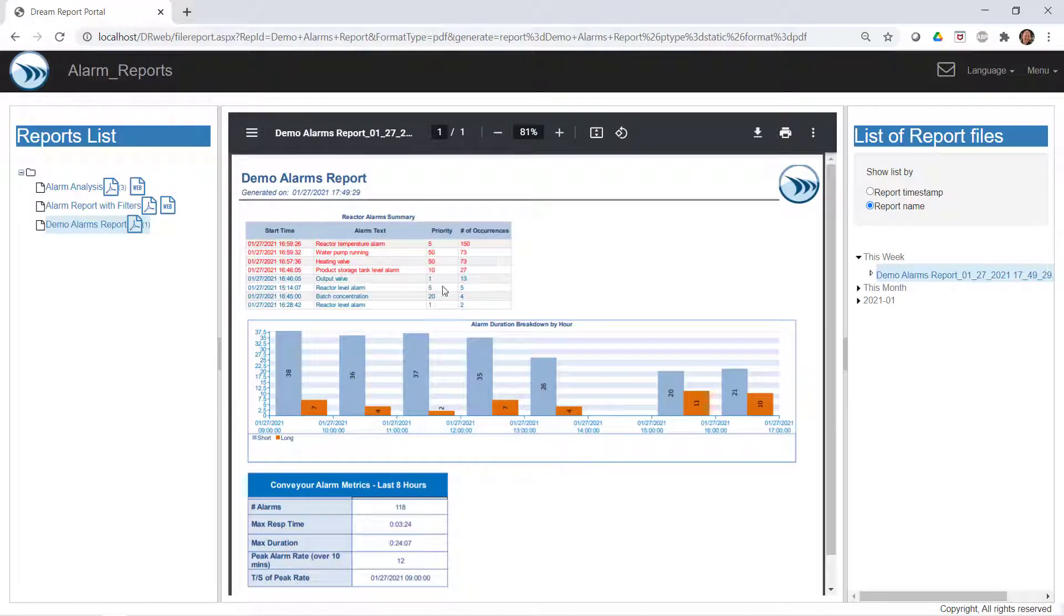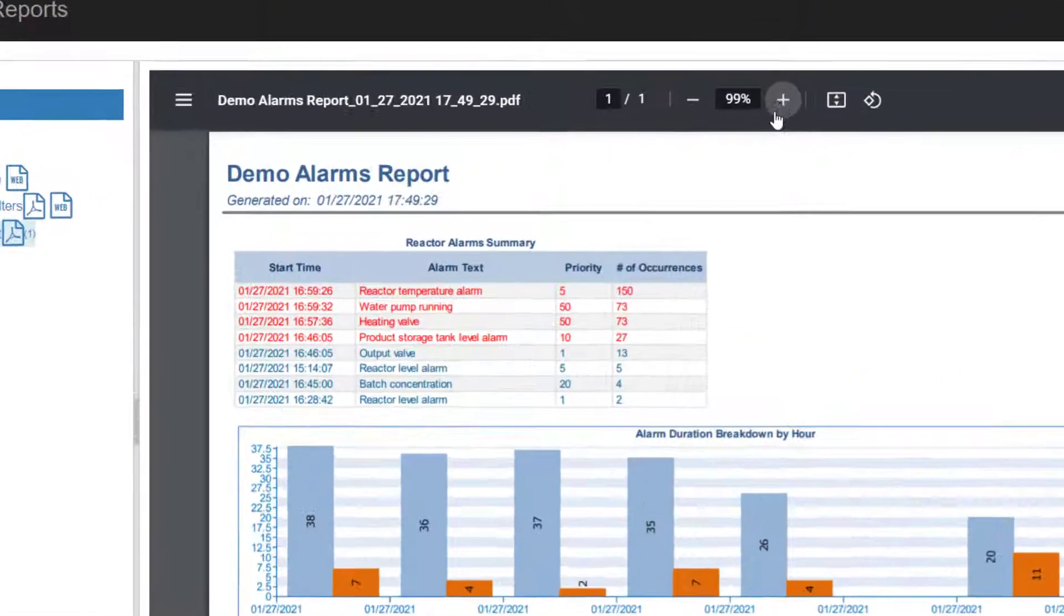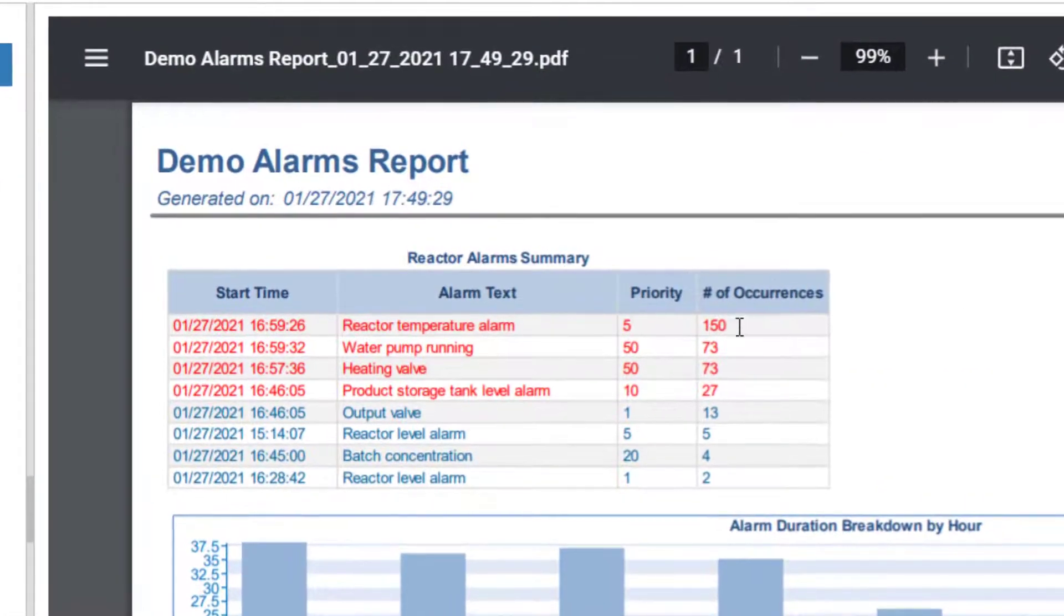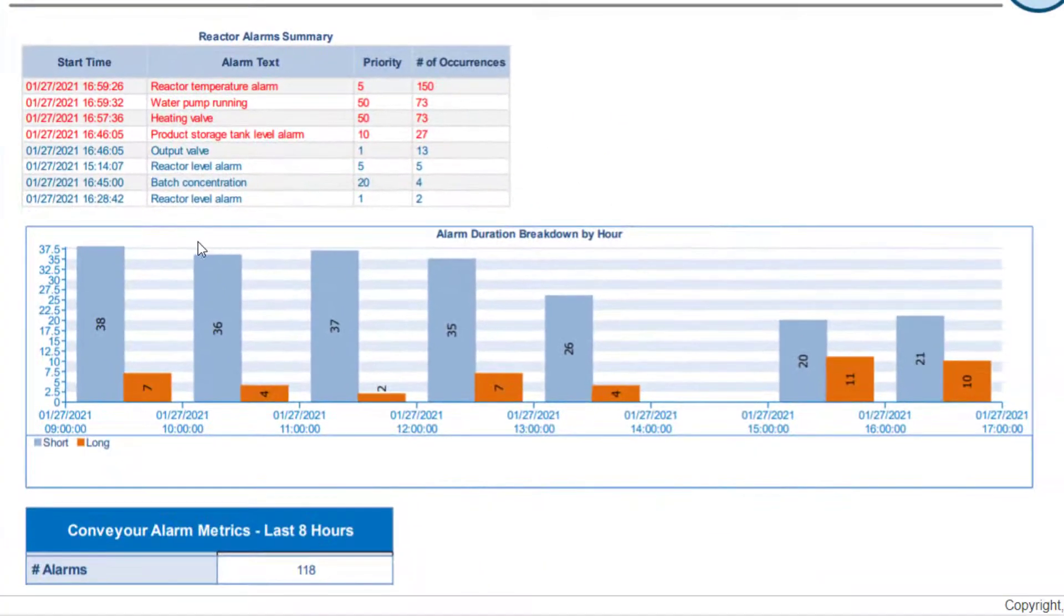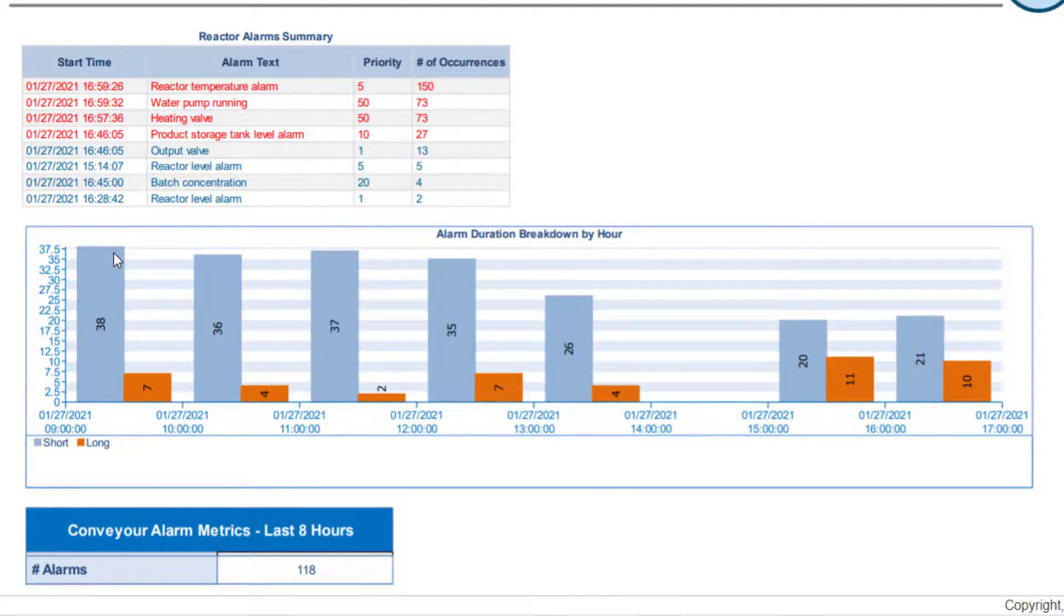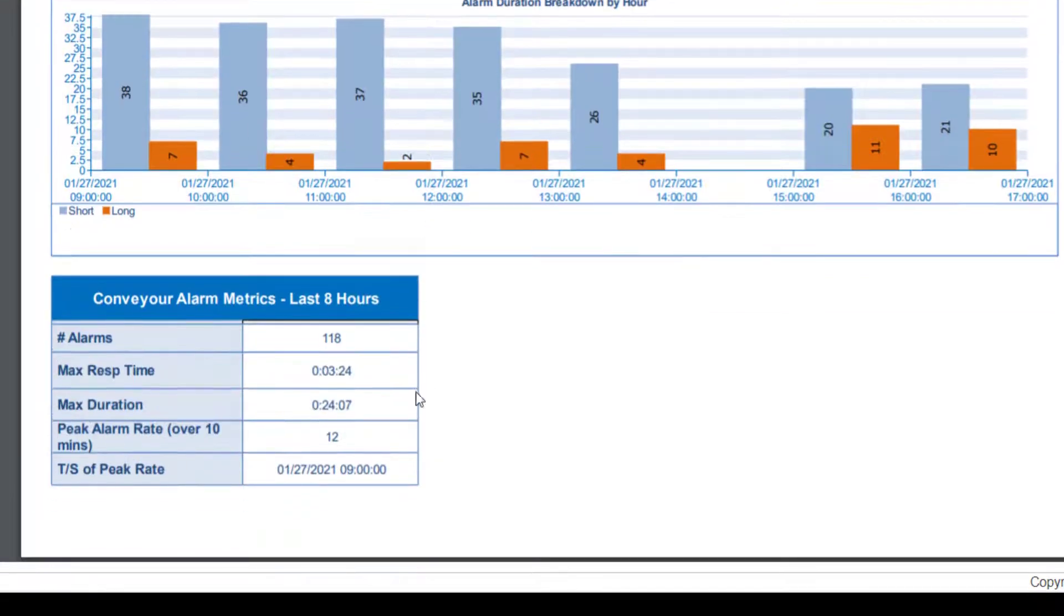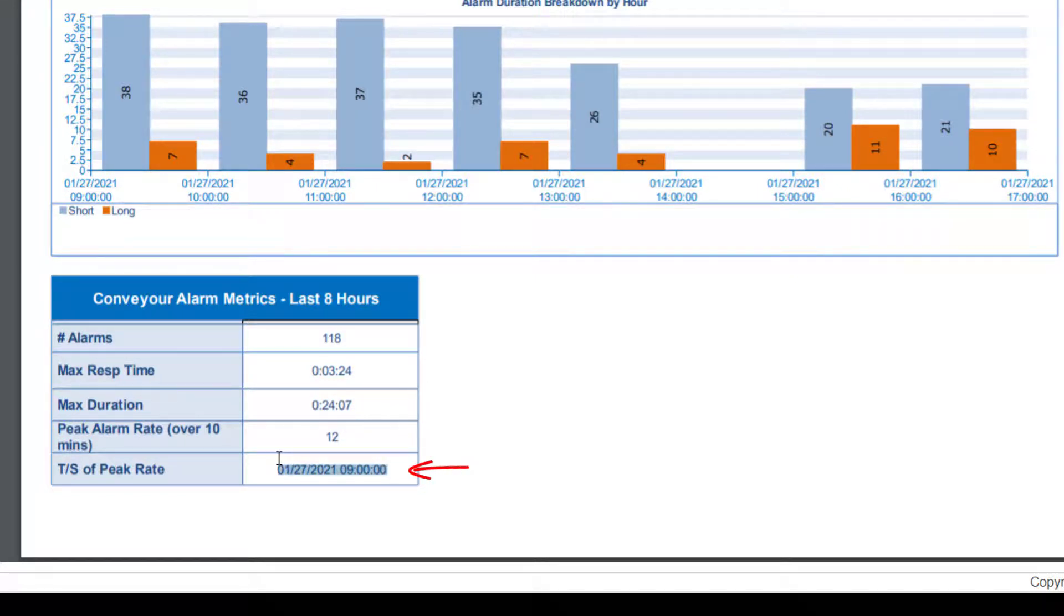And let's take a look at how all these alarms have been put into context. We see the big hitters with respect to alarms in our reactors area. Looks like we need to focus on our temperature alarms. Looking at the hourly bar graph, we're definitely seeing a lot of high priority, chattering alarms around certain periods of the day. The longer duration alarms seem to be in check. And in the summary of our conveyor alarms, our alarm counts look relatively low for the day. But we can observe that the peak period of alarms in a 10 minute period started at this point in time.